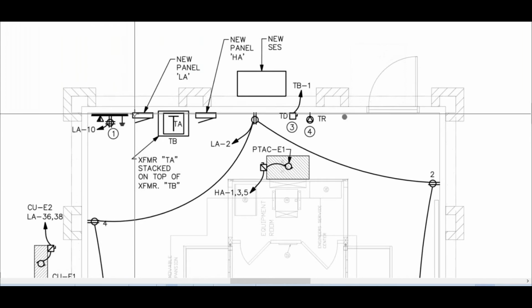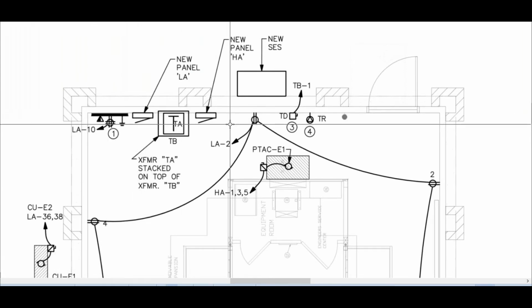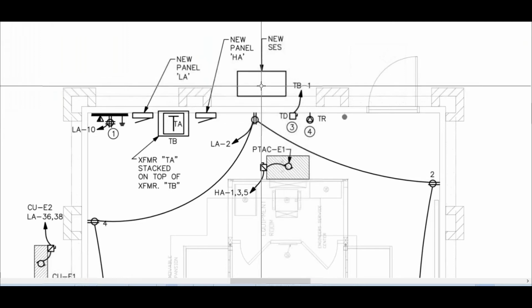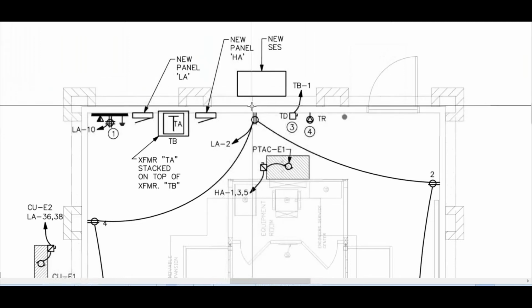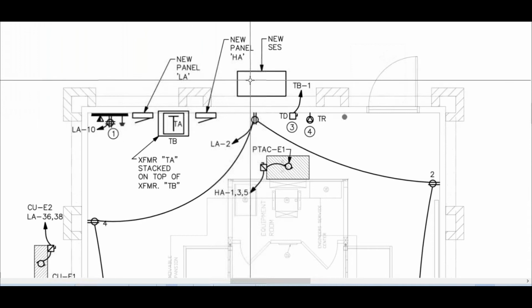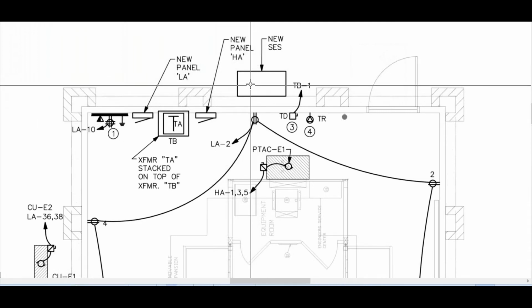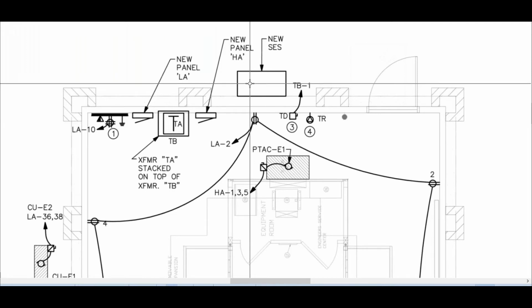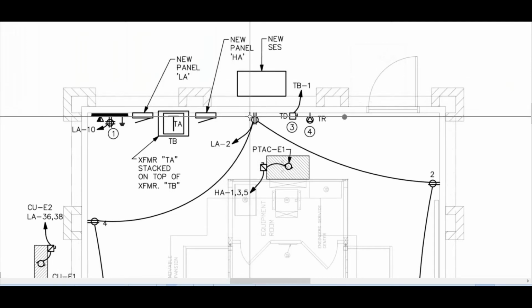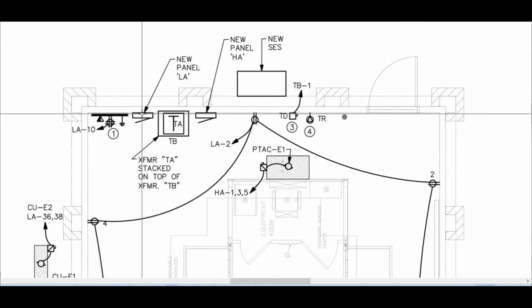In order to do so, here's something else to pick up on. There's a lot here. You have to penetrate this wall right here. You'd probably come out of the top. This is the way I would estimate it: come out of the top, set a Myers hub, run your conduit up through the wall, over and down into panel LA, which is also a 600 amp panel.